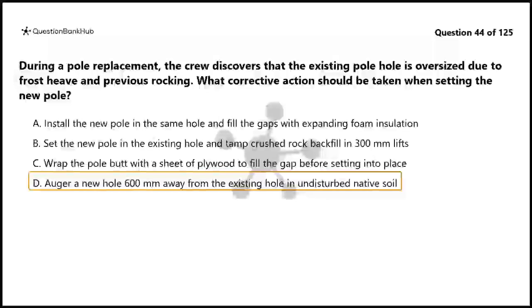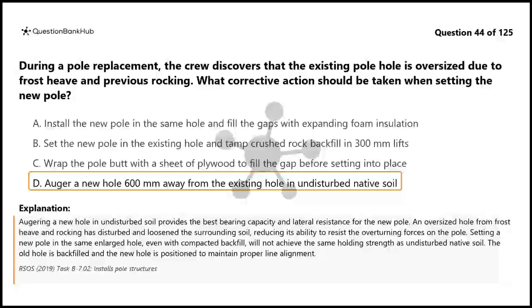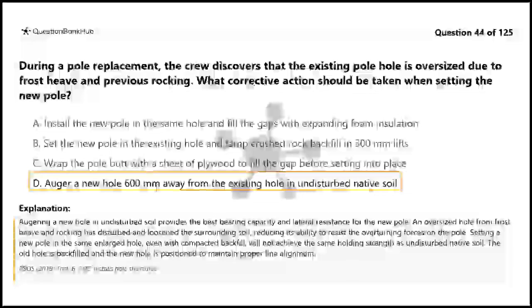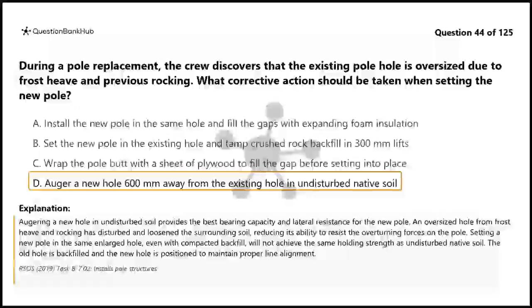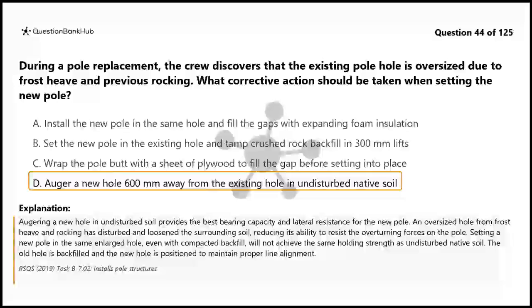The correct answer is D. Augering a new hole in undisturbed soil provides the best bearing capacity and lateral resistance for the new pole. An oversized hole from frost-heave and rocking has disturbed and loosened the surrounding soil, reducing its ability to resist the overturning forces on the pole. Setting a new pole in the same enlarged hole, even with compacted backfill, will not achieve the same holding strength as undisturbed native soil. The old hole is backfilled and the new hole is positioned to maintain proper line alignment.